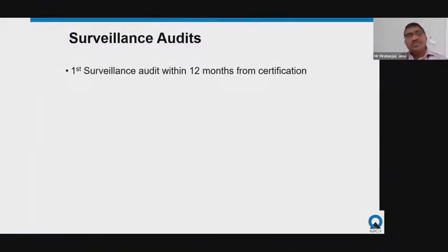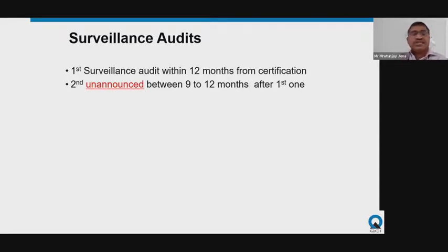Once certification is granted, the first surveillance will be within 12 months for level 1 and level 2 schemes. The second surveillance is a very specific scheme requirement, unlike ISO 9000 or ISO 13485 certification—it is unannounced, but expected 9 to 12 months after the first one. So as industry going for certification, once you are initially certified to level 1 or level 2, expect that within 9 to 12 months after the first surveillance audit, the certification body will visit your premises unannounced to carry out the second surveillance.